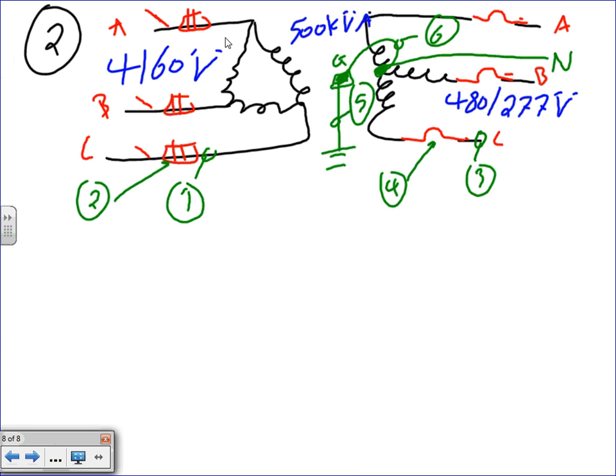Okay, so we're gonna size the feeders on the primary and secondary, the fuse on the secondary and primary, and the bonding jumper, and the grounding electrode conductor. Is this a separately derived system, Camille? Separately derived system? Yes, it is a separately derived system. I'm creating a new neutral.